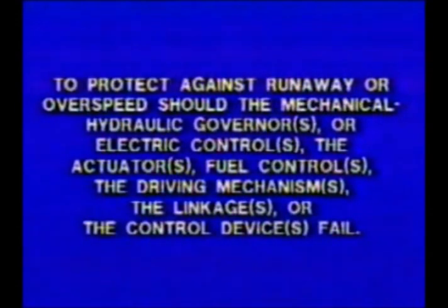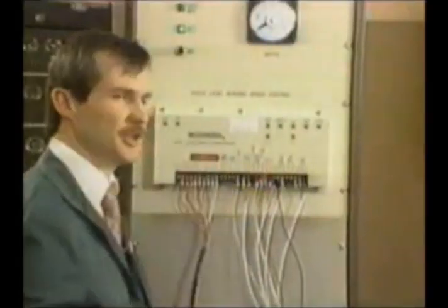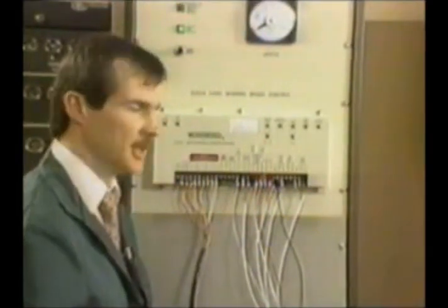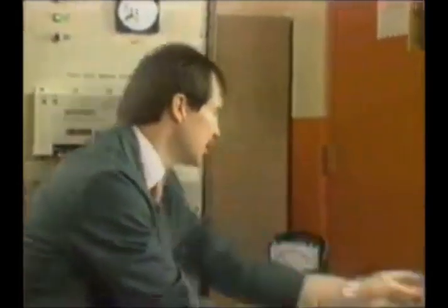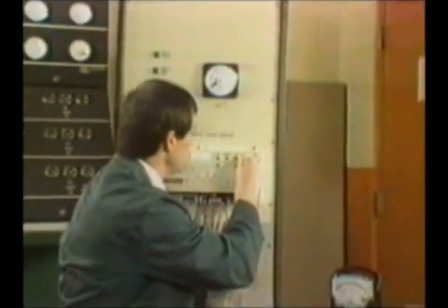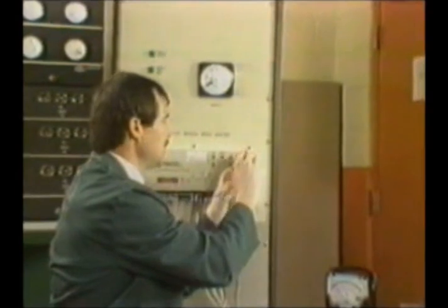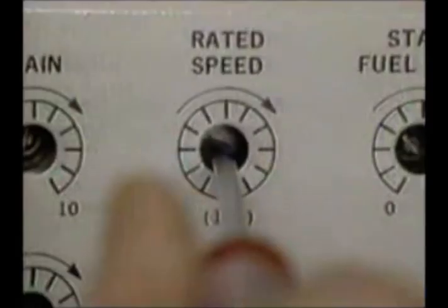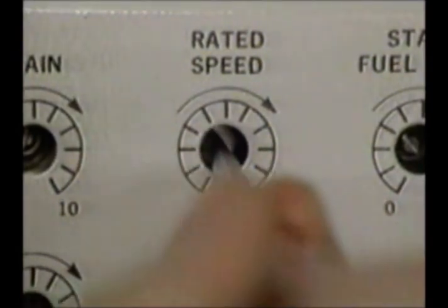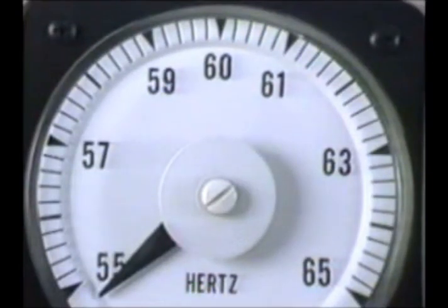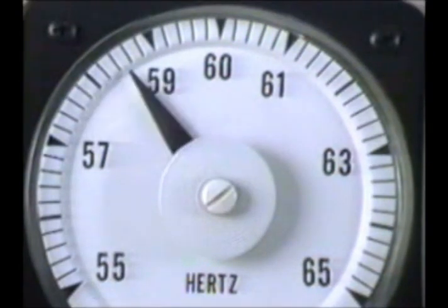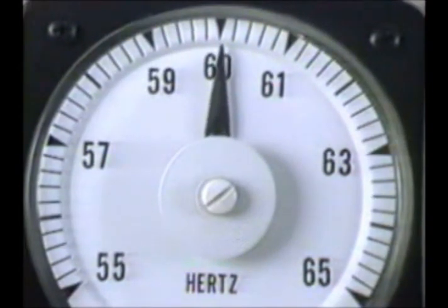We'll start up at a real low speed, and then I'm going to use my Hertz meter to see when I finally get up to 60 Hertz. So I'm going to start the unit. It started up at a real low speed. Now I turn my rated speed potentiometer clockwise. You can hear the engine picking up speed. We're on the Hertz meter now and set it up for 60 Hertz. So now my Hertz meter is reading 60 Hertz and we're controlling the engine.